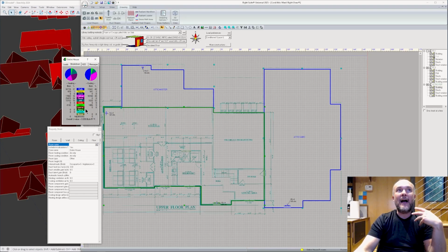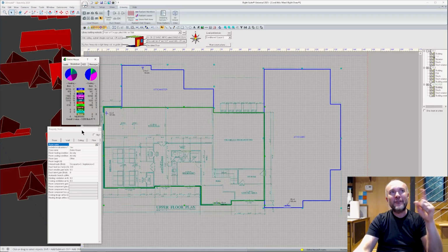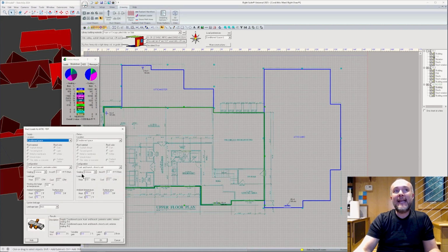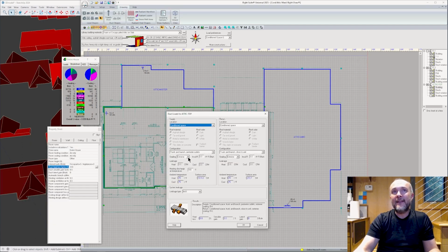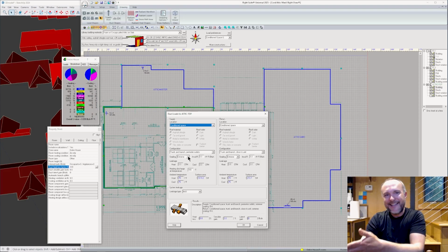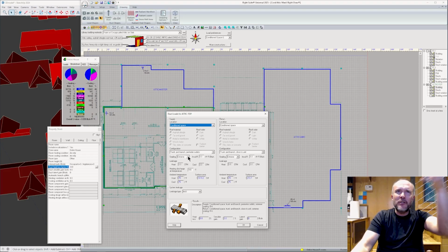I like that because now I know for a fact that they're not going to be bleeding my heat out into the attic that I'm not sure what temperature it's going to be up there. Remember when we set those, we'll do that again with the temperature differential between the house and the attic space, but it's a guess all the time. Okay, so here I'm going to go ahead and say that where I had it set to was most duct systems that I'm inspecting and working on designing for are going to be extremely tight because ductwork is plumbing for air and you don't want it bleeding out all over the place because you want it to get to the fixture that you're delivering it to. That's why we're doing all this, right?